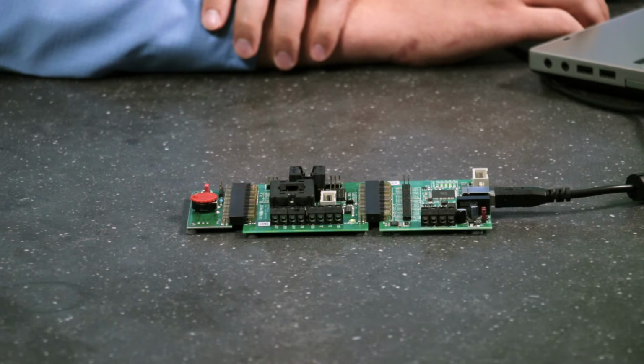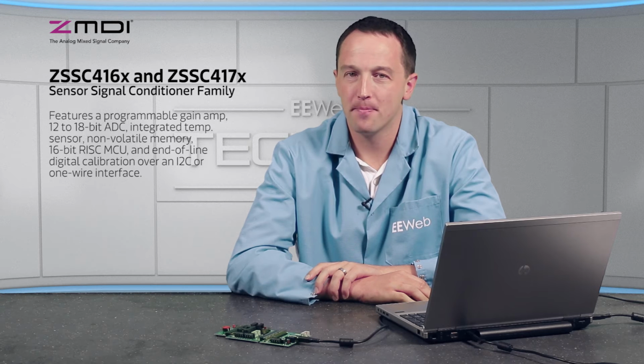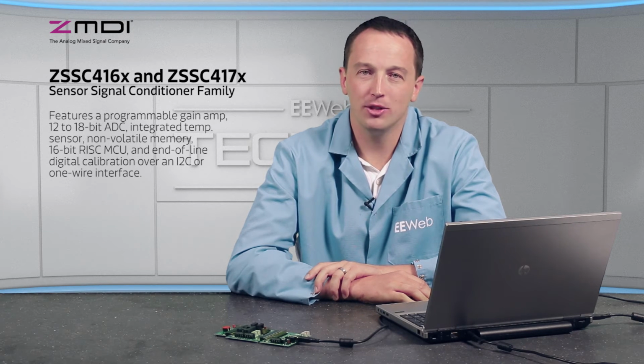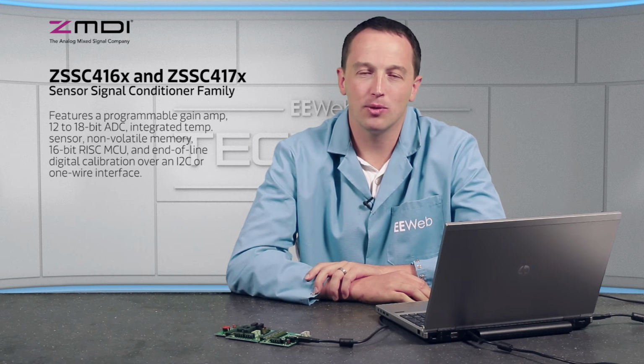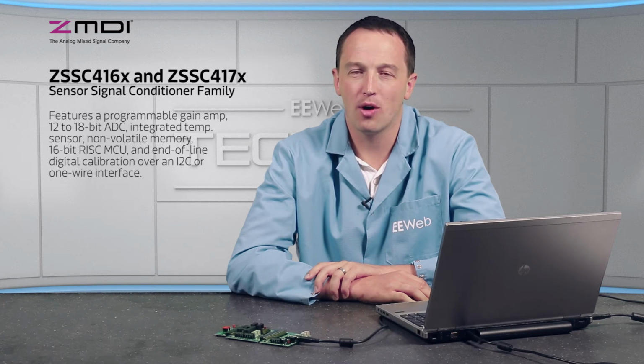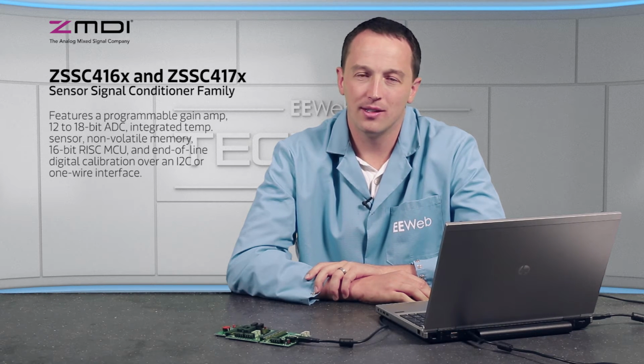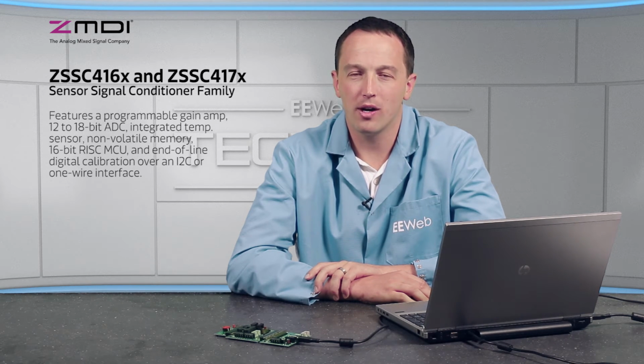The ZSSC416x and ZSSC417x feature a widely programmable gain amplifier, a 12 to 18-bit ADC, an integrated temperature sensor, non-volatile memory to store calibration coefficients and configuration data, and a 16-bit RISC MCU that uses the calibration data and temperature measurement to compensate for offset, thermal drift, sensitivity variations, and non-linearity. End-of-the-line digital calibration over the I2C or one-wire interface improves calibration accuracy and reduces assembly cost and complexity.